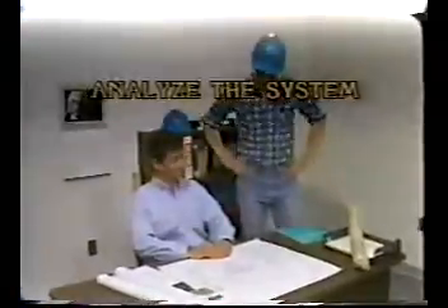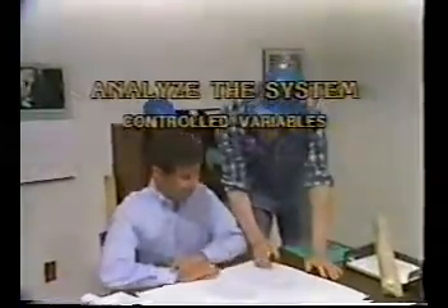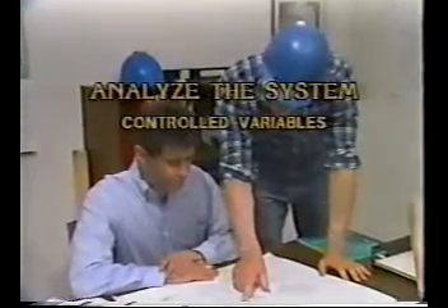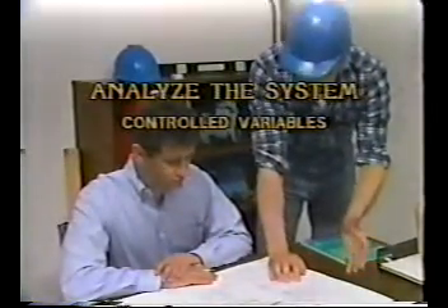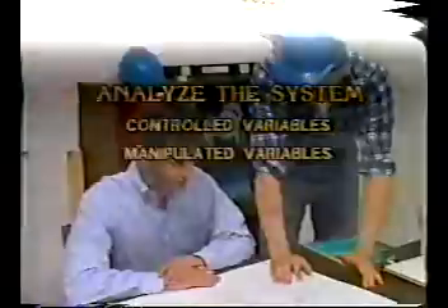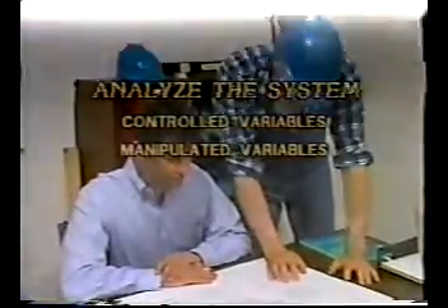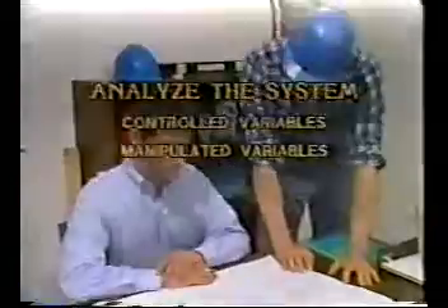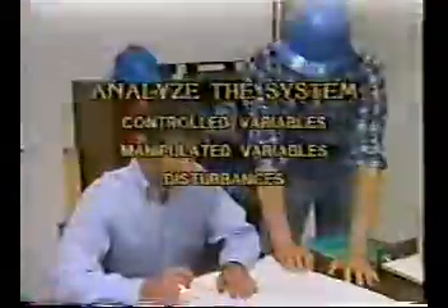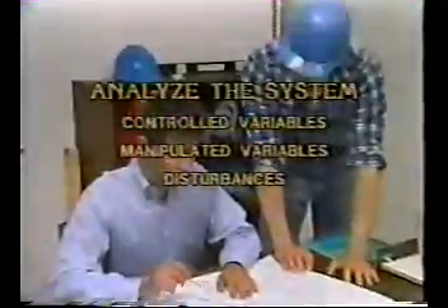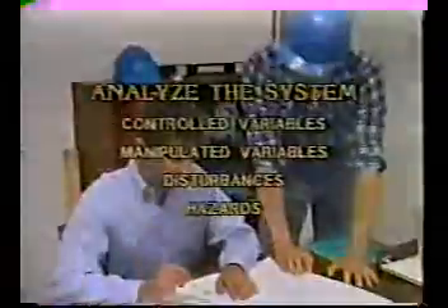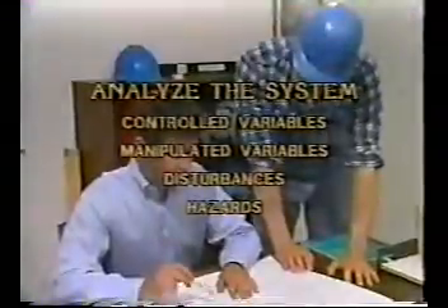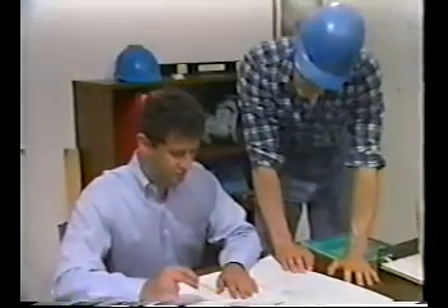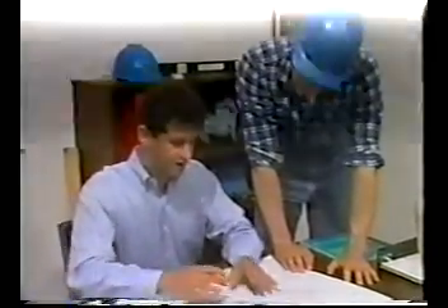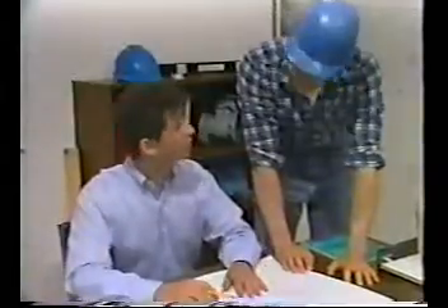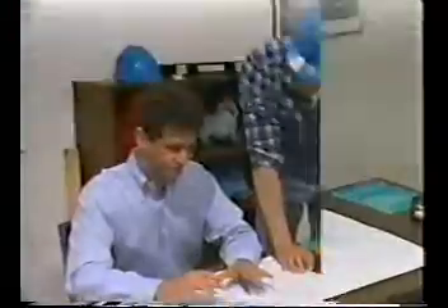Ask questions about the controlled variables, what their ranges are, how closely they must be controlled, what's the penalty for deviation. Also, find out about the manipulated variables. How can they be best paired with the controlled variables? Discuss disturbances that can affect the process and how they might affect process control. And of course, don't forget about hazards associated with the process. Use the knowledge you gain to identify any alternative control schemes that may result in reduced cost or improved control.